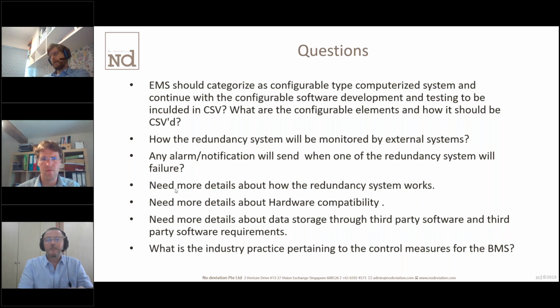Because the BMS is what controls the temperature, I think when we do a change of set point or control in the BMS—keep in mind the EMS just monitors, so it will tell you whether you were right or wrong, but the BMS makes it happen—any change in the BMS system needs an engineering change control and an assessment of whether it touches the quality area. A discussion then needs to happen with the QA of the site about how this is going to be executed and closed.